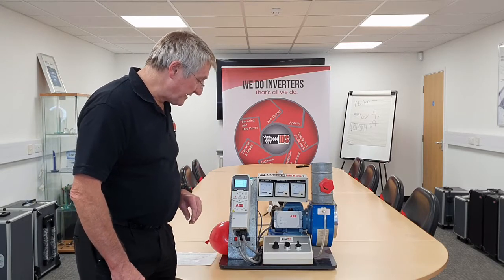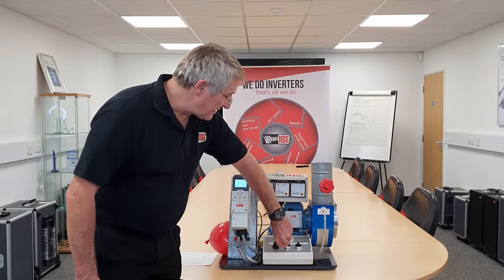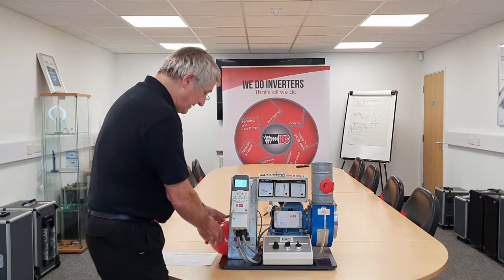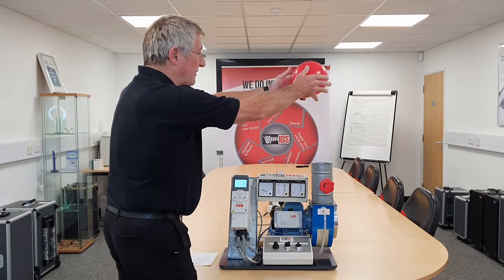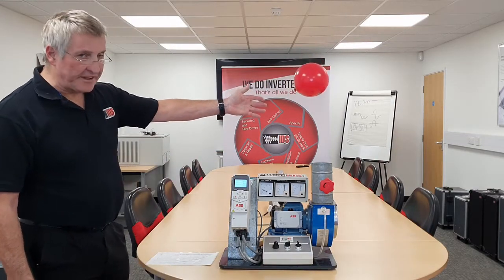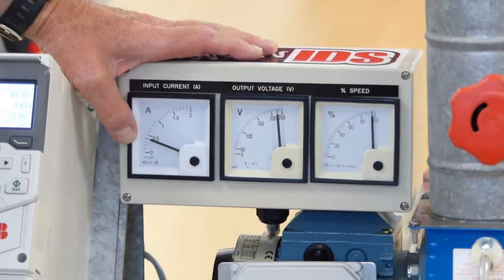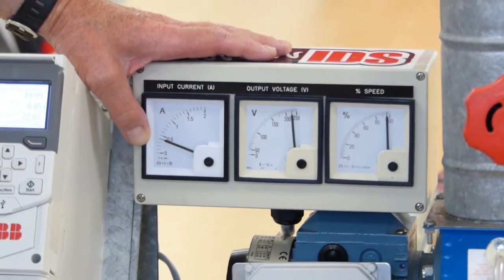So we are going to control firstly with a damper. I am going to turn on the fan and close the damper to reduce the air flow. The height of the balloon represents the flow — you can see there we are around 2 feet above the little piece of duct. But what is happening here is we are now taking 0.4 of an amp.